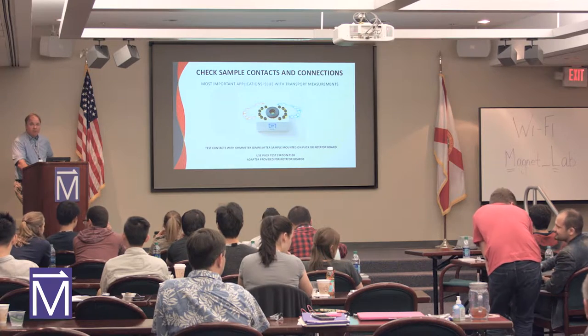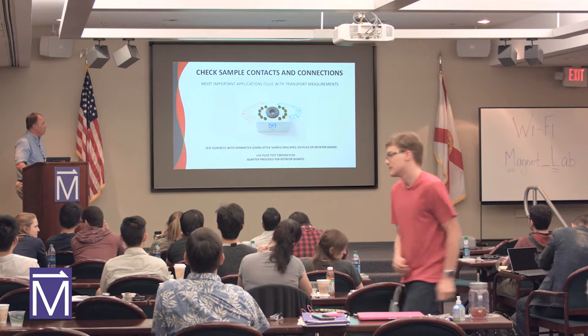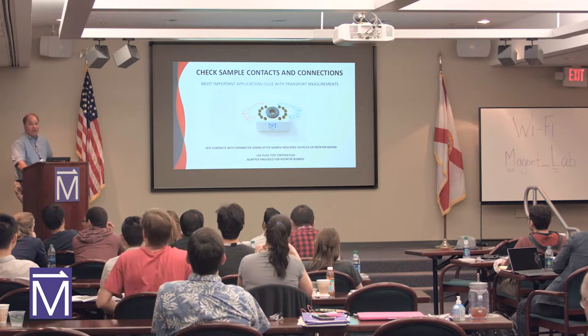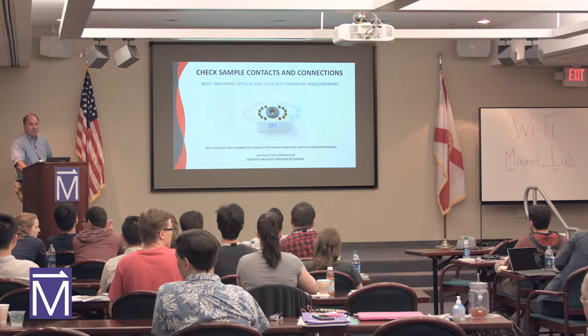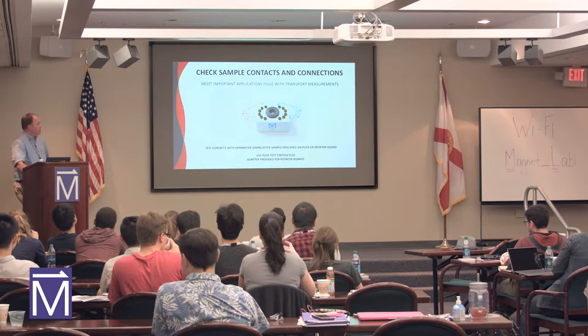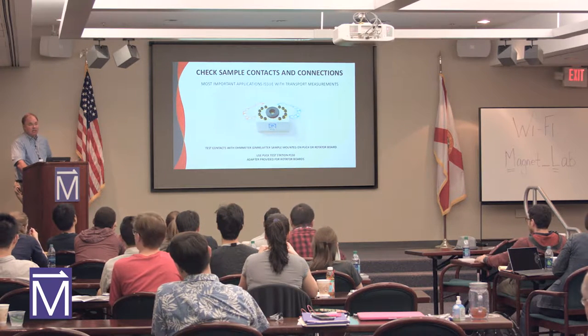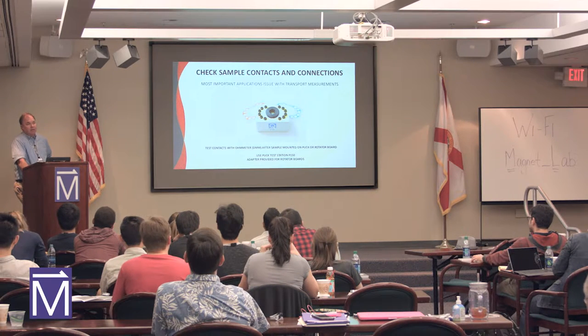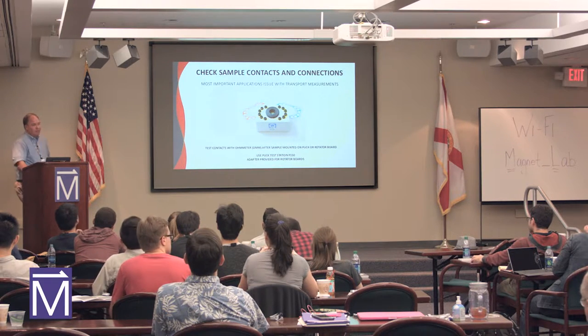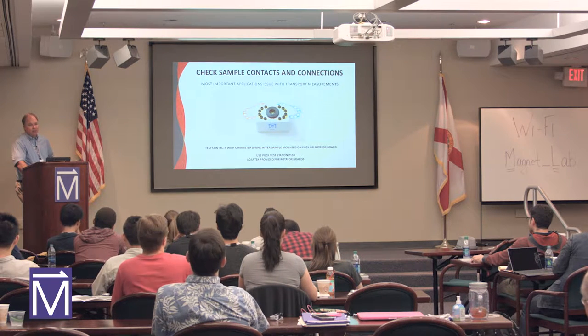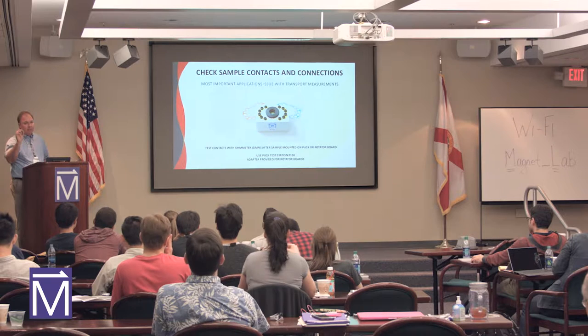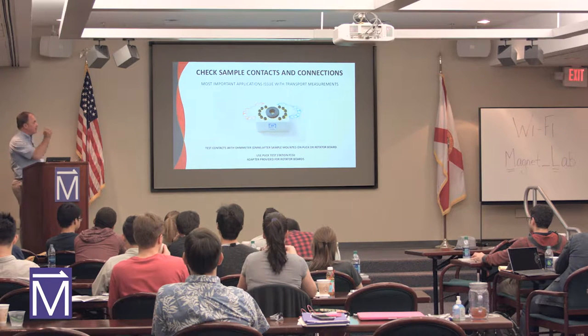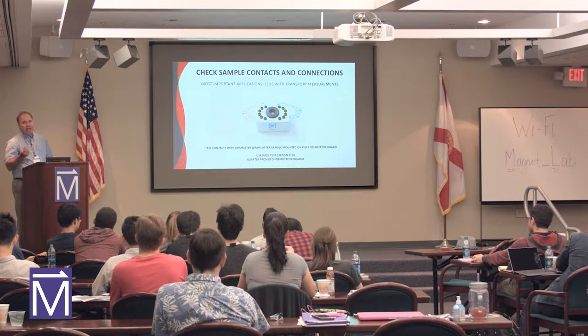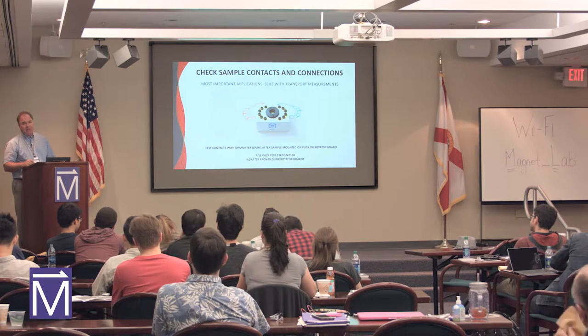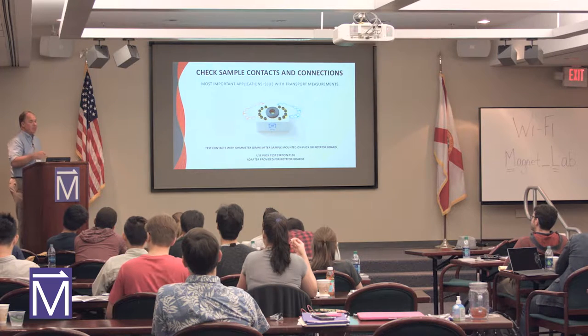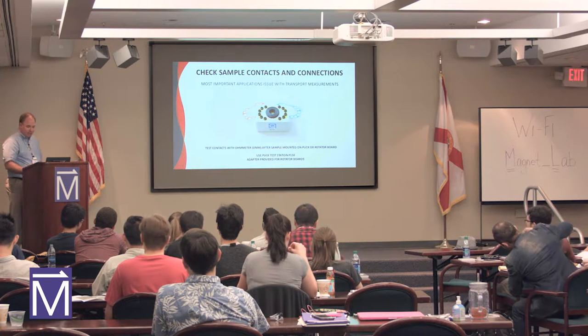What we provide is a little breakout box with the instruments, and there's a little overlay that fits on the breakout box. Depending upon what type of experiment you want to measure, we give you the pinouts. So if you choose the heat capacity system, you can mount your sample, put the heat capacity overlay on, and then make your electrical connections on the bench. Mount your sample on the puck, put it in the measurement jig, and then you can use an ohm meter, multimeter, or Keithley meter to make your electrical contacts at room temperature. Do you have good contacts? And then you can move it into the system.